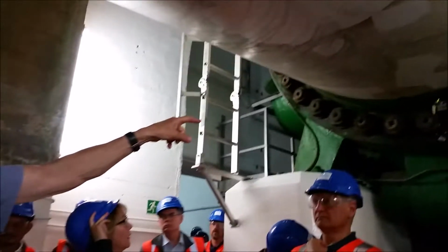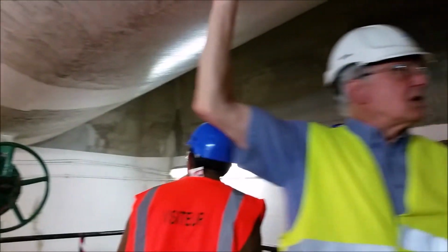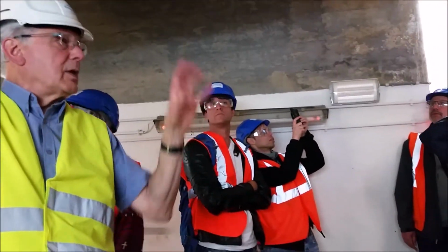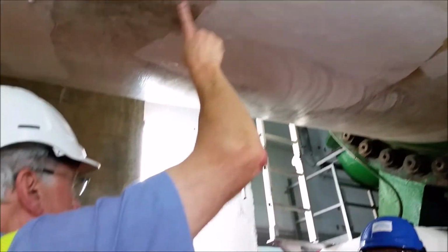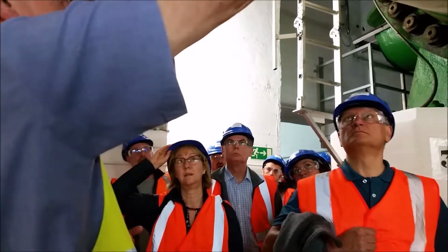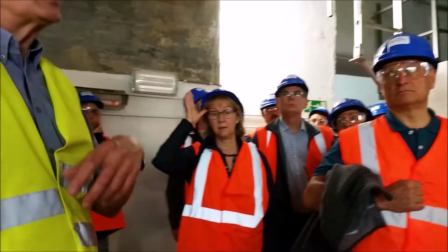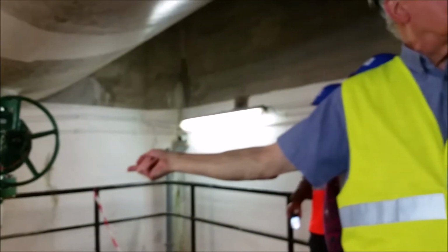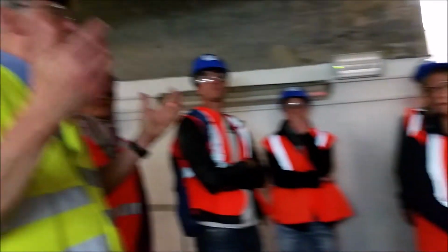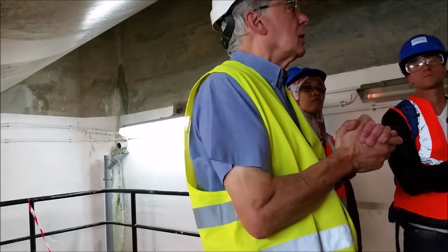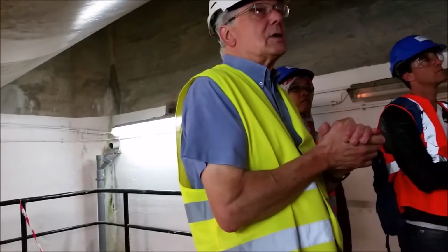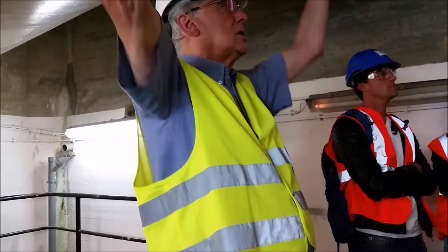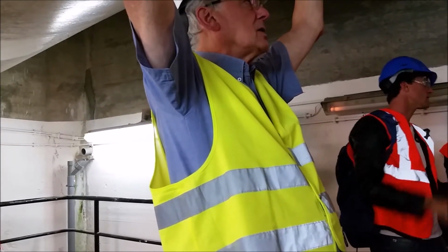So that is the only valve we have between the upper reservoir and the turbine. The upper reservoir is 300 meters higher than we are here, so at this point, if we measure, we have 30 bar. That's also the reason why, for security, we are using the pressure of the water to close this valve. We take a part of the water here, at 30 bar, to close it, for example if we have leaking or problems with the electric power supply. This pipe has a diameter of 3 meters.